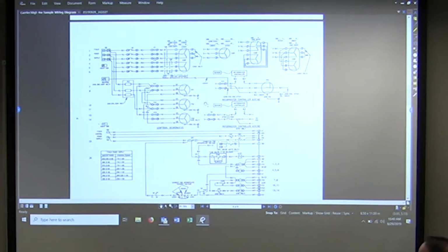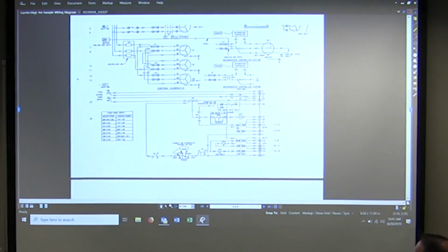Okay. I have here some fan motors, FM, and how they're wired up, and they have FC1, FC2, FC3 for the contacts that turn those on and off. Okay. There's a motor master controller wiring, if you're using one of those, that shows how to tie that into our FM1. Down below here, again, this is all the higher voltage stuff.